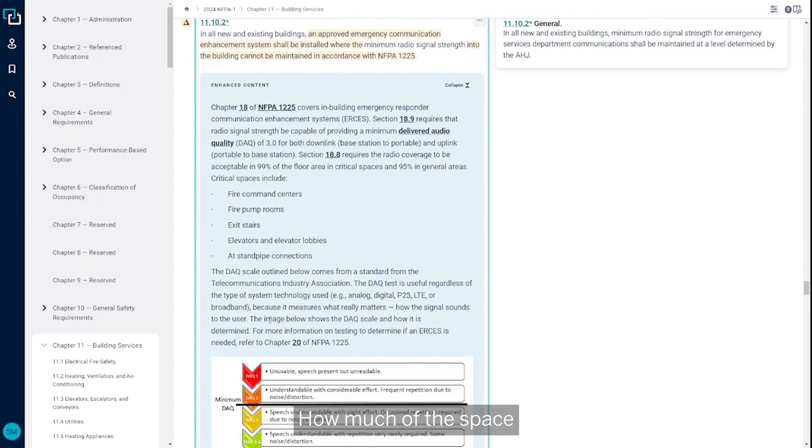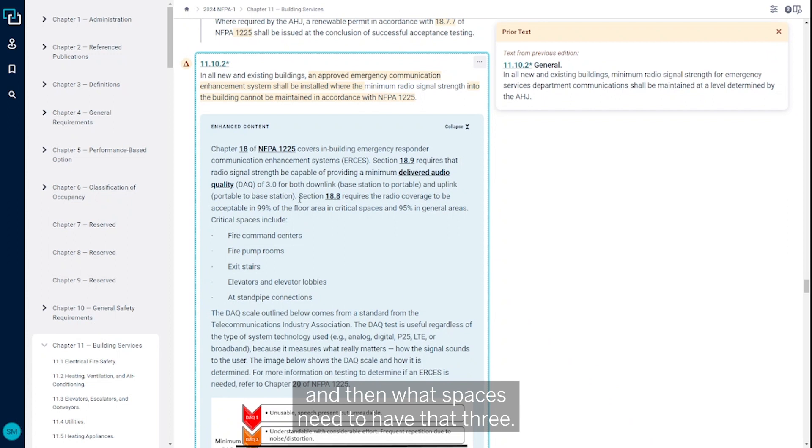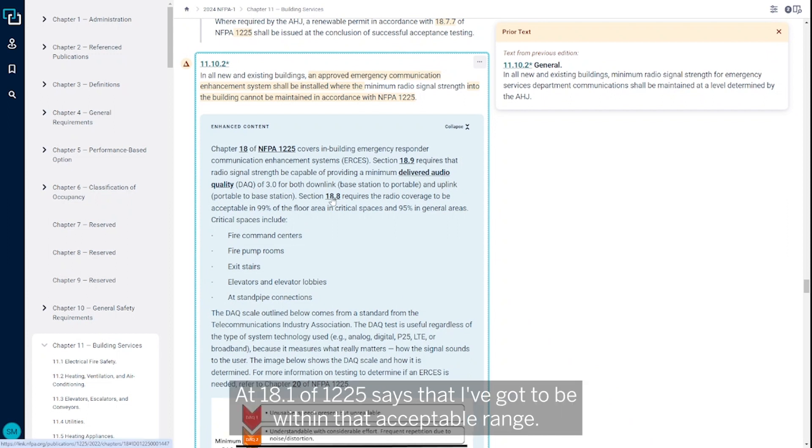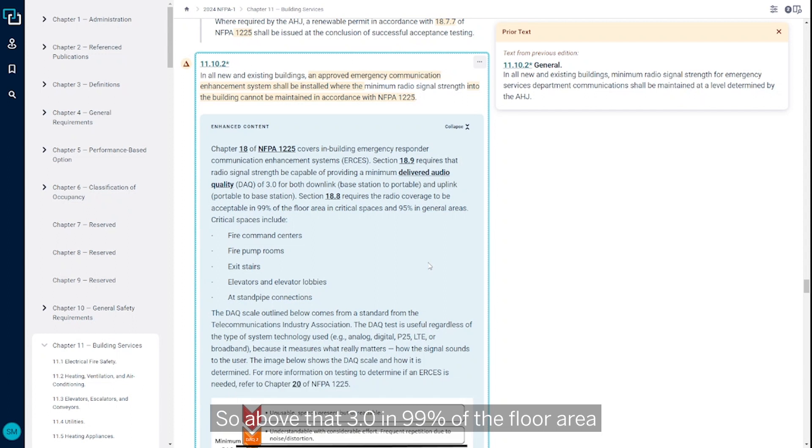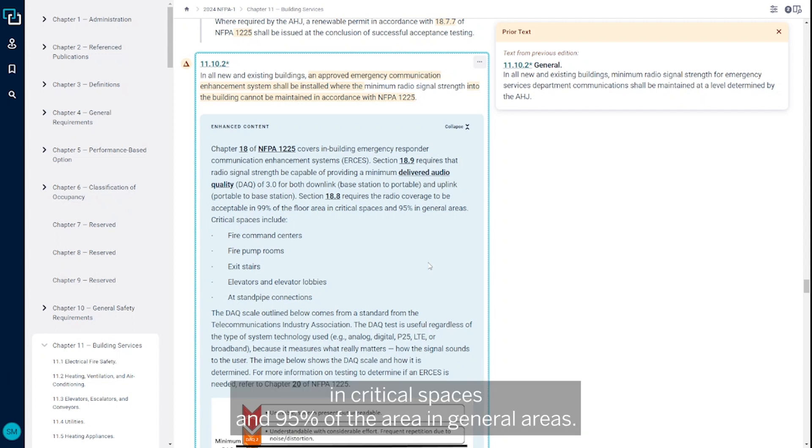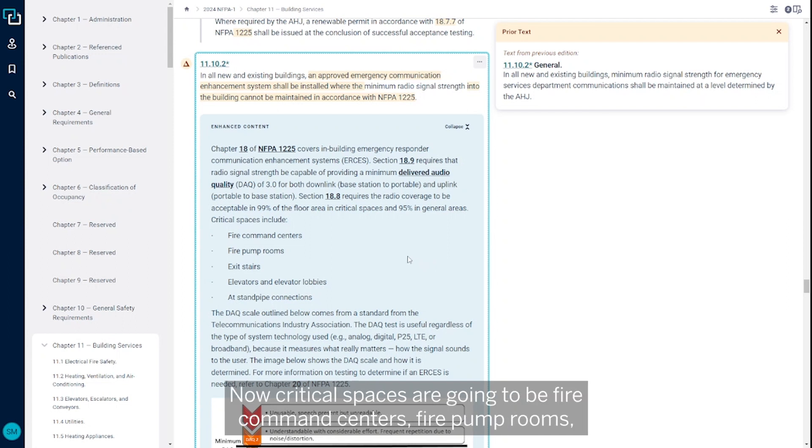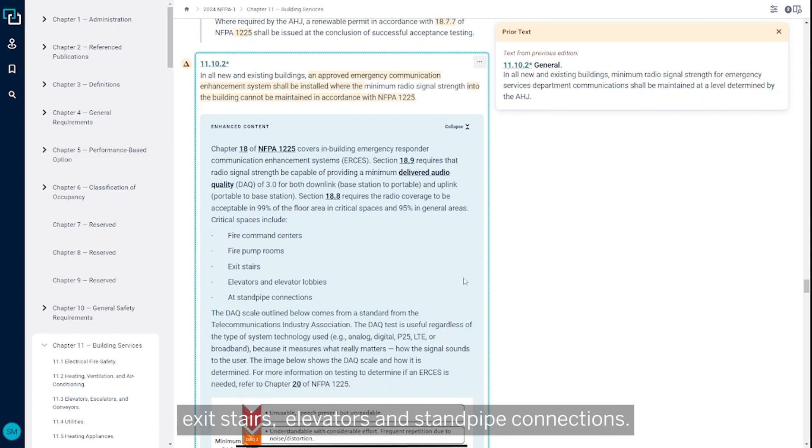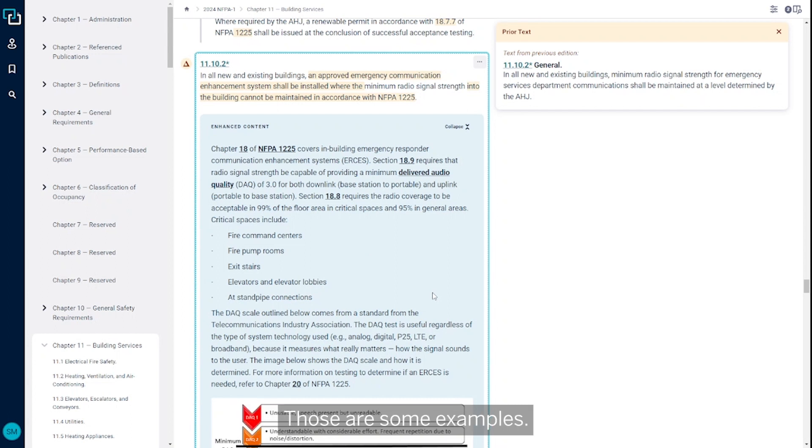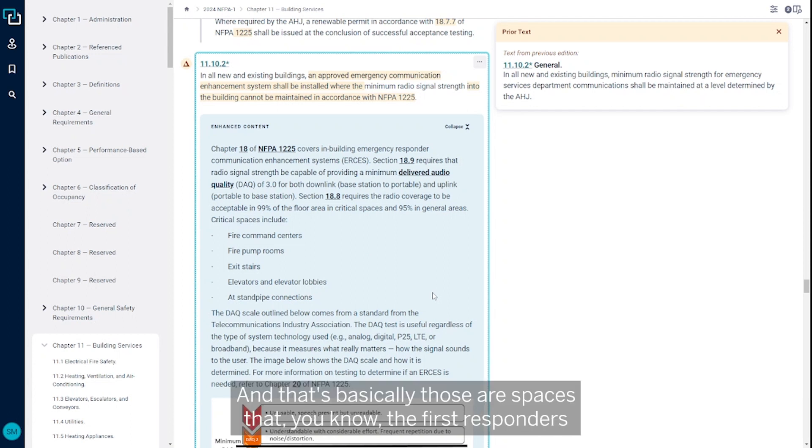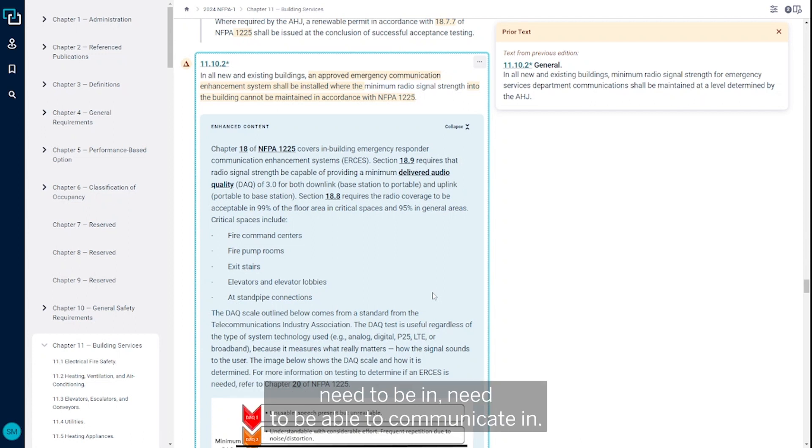How much of the space and what spaces need to have that level three? Section 18.1 of 1225 says you've got to be within the acceptable range—above 3.0 in 99% of the floor area in critical spaces and 95% in general areas. Critical spaces include fire command centers, fire pump rooms, exit stairs, elevators, and standpipe connections. These are spaces first responders need to be and communicate in.